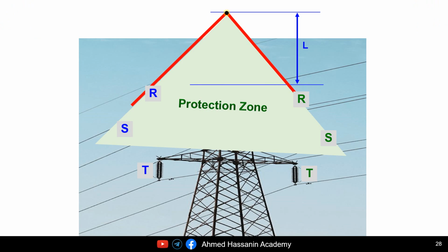This means that as the width of the tower increases and the horizontal distance between the phase conductors increases, should we always increase the height of the shield wire or earth wire or ground wire? Of course not, because this would imply that for transmission voltages such as 500 kilovolts, the height of the shield wire or earth wire or ground wire might need to be as high as the tower itself, an impractical solution that would result in extremely high construction and economic costs.